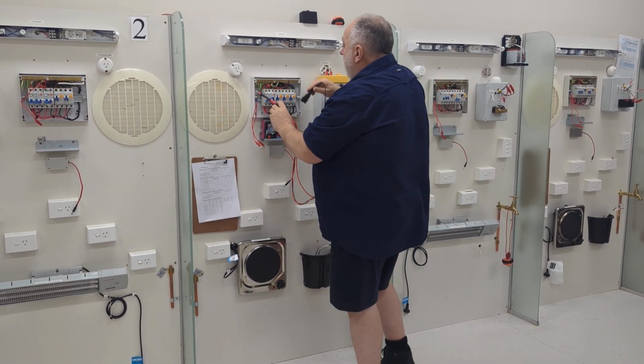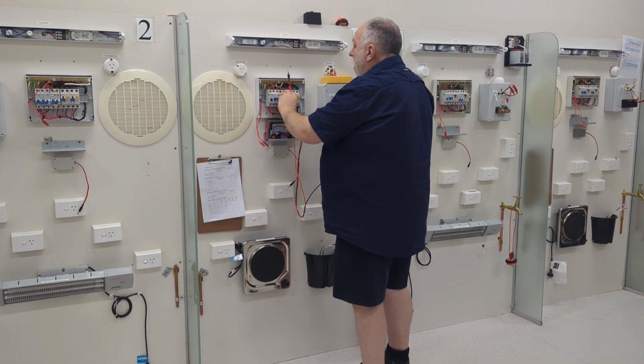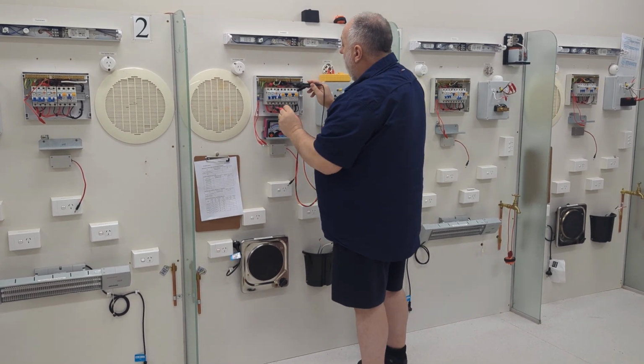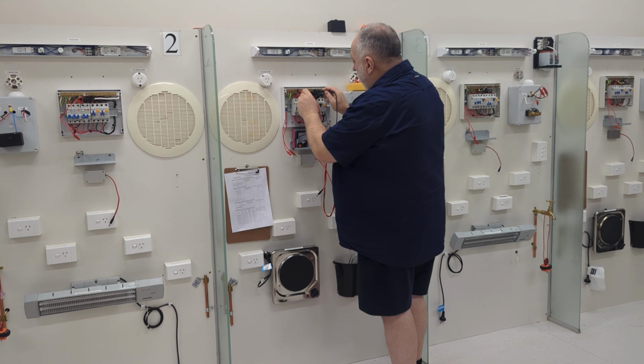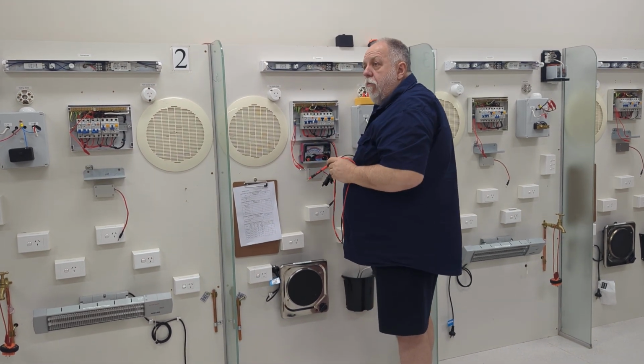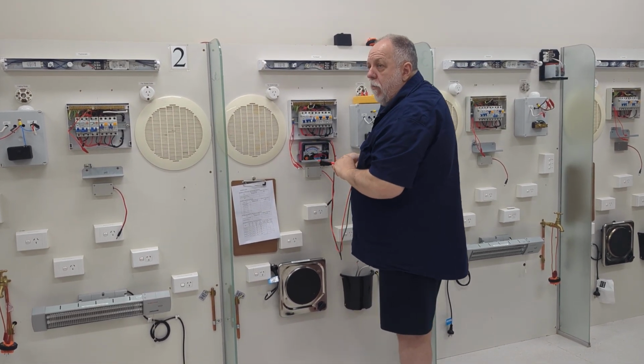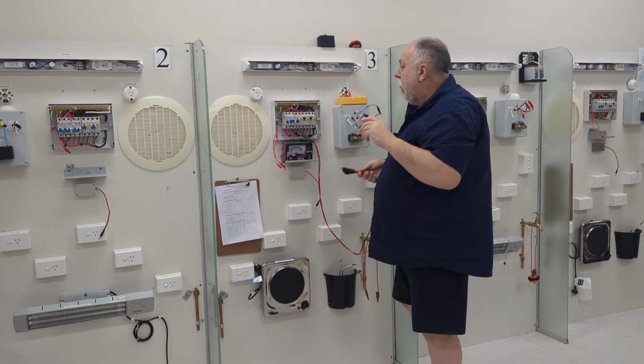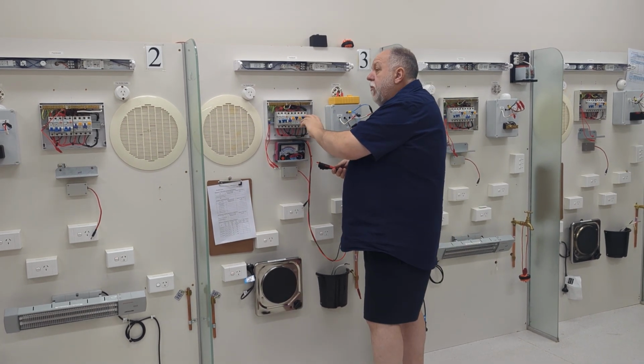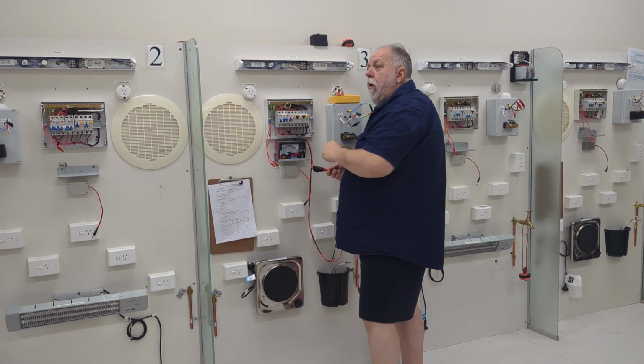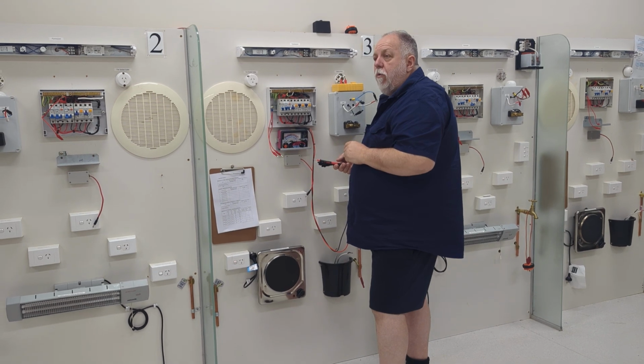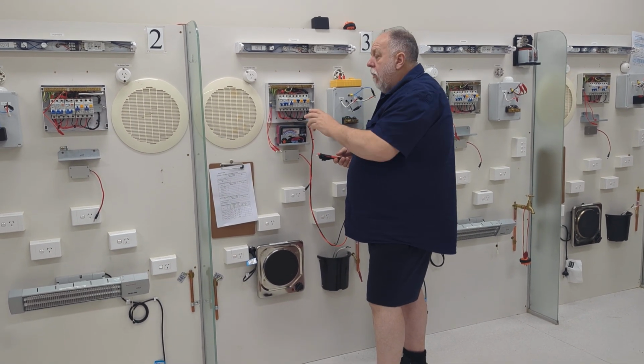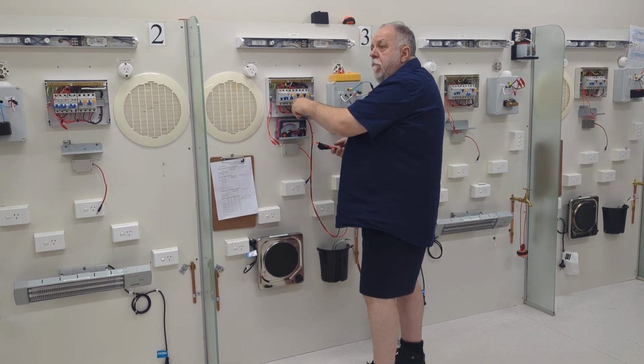If I went to test the whole installation, I could actually turn that back on, leave the lighting breaker on, and I reckon if I go between earth and the other one, it's reading infinity, or 50 meg plus, don't use the word infinity, sorry. All right? So that means it's okay, but as soon as I turn that breaker on, I'll actually introduce the fault again, and it'll pull it back down. So I've isolated to the lighting circuit.